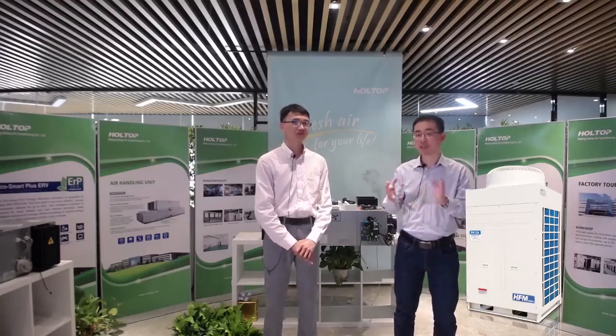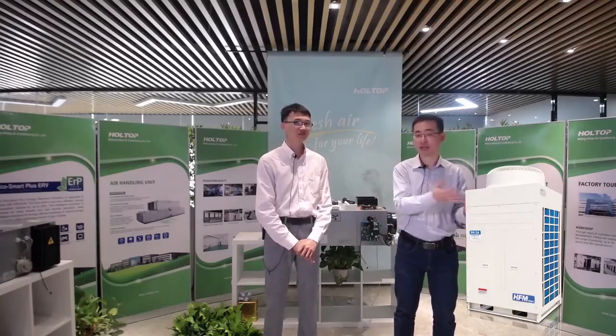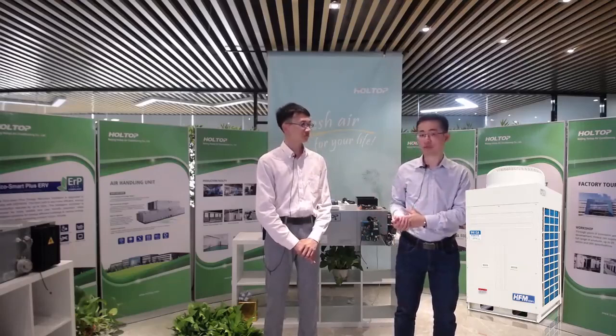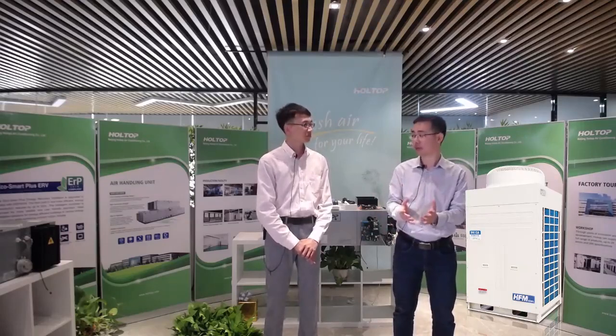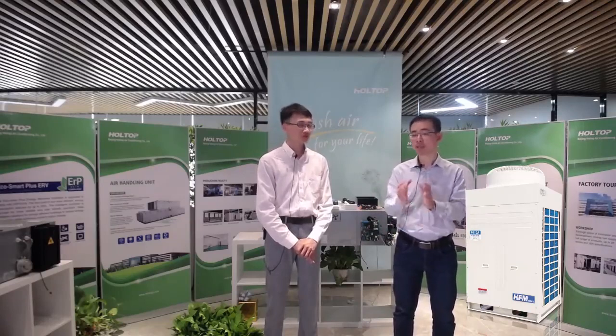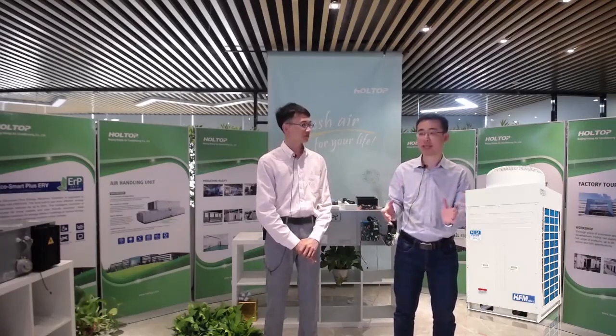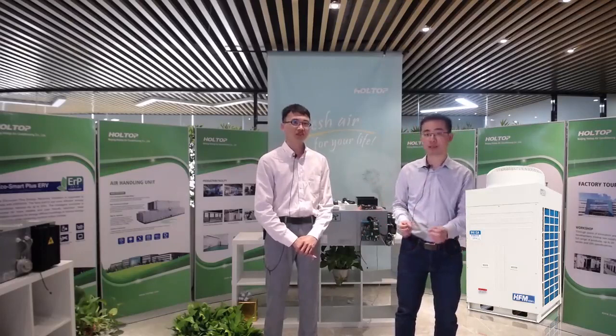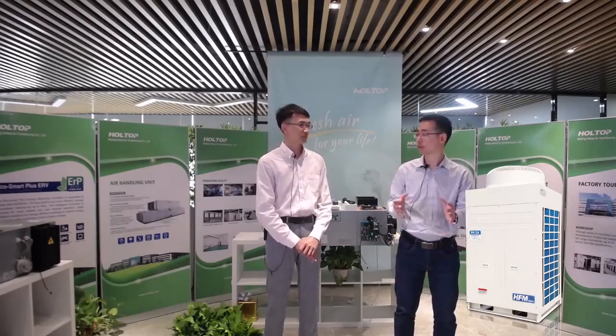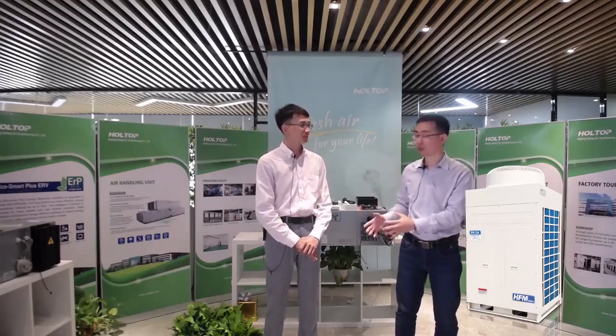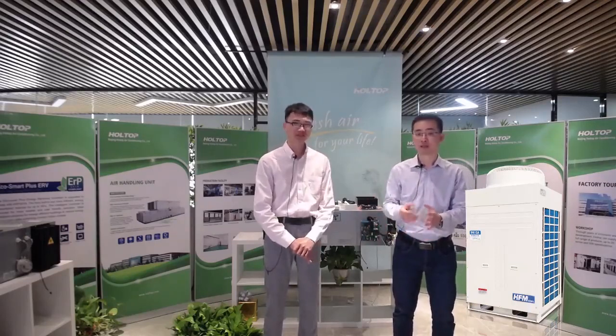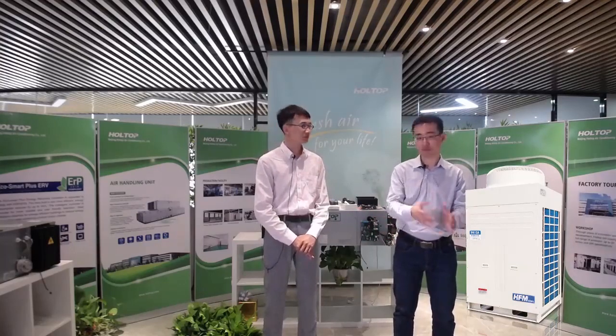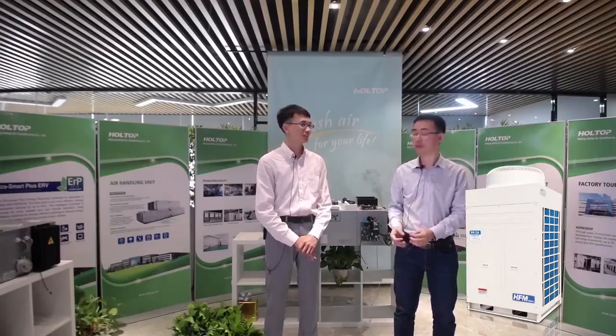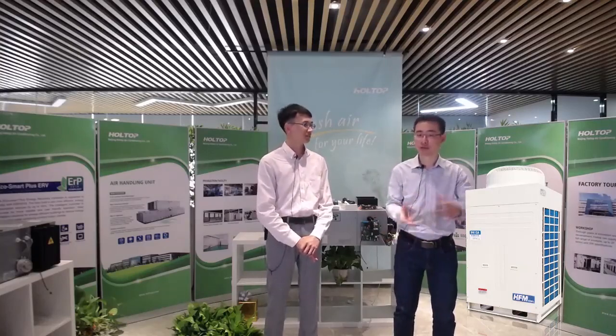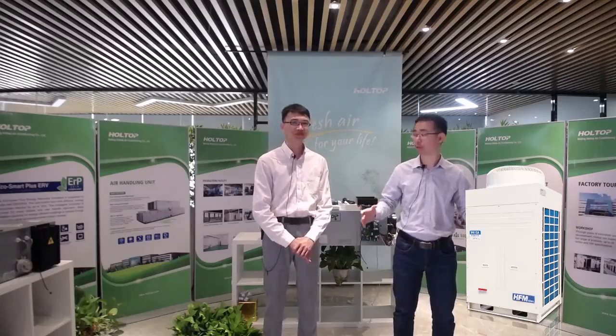But this pre-cooling is not enough. For example, when outdoor is 35 degrees and indoor is 25 degrees, after heat recovery the supply air can be around 28 degrees. But 28 degrees is not enough for the supply air of the industrial factory. So the customer needs to air-condition this 28 degree air. At this time, a DX coil inside these AHUs and the condensing units can solve this problem. The DX coil can reduce it from 28 to 25 or even as low as 23. So we can introduce this air into the factory to make the whole production process meet the requirement.